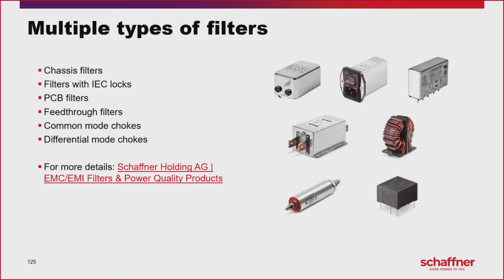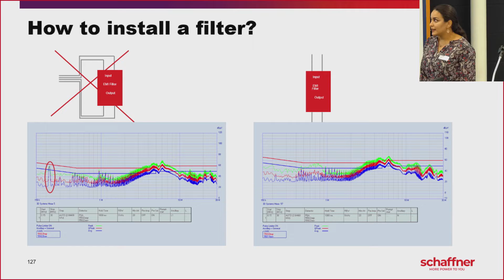So before answering that question, I would like first to tackle another problem that is even more important, I would say, which is how to install the filter. Because from my own experience at least, I can tell that 80% of the problems that we see are actually cabling problems. They are not even problems about the filter itself or about dimensioning the filter. It's about the cabling itself. So I would like to give you some hints about the cabling and to make sure that you pick up the right filter. So the first thing is to keep the cables as short as possible.